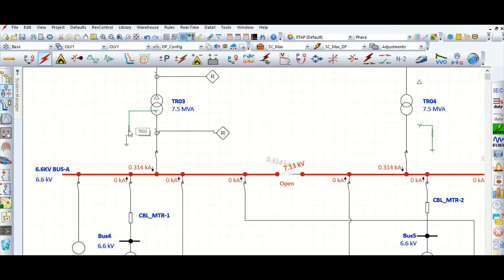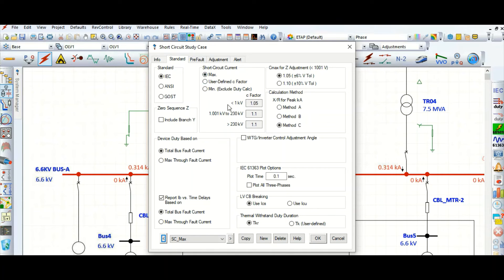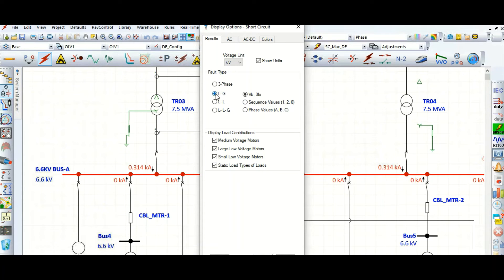We limited the ground current to 300 amperes with this NGR — neutral grounding resistance. The reason it is showing 314 instead of exactly 300 is because of the c-factor. Go to the case editor — for the 6.6 kV system, the c-factor is 1.1, so c-max is 1.1, which is why the result comes to 314 amperes. You can verify this from the display option for single line to ground fault.